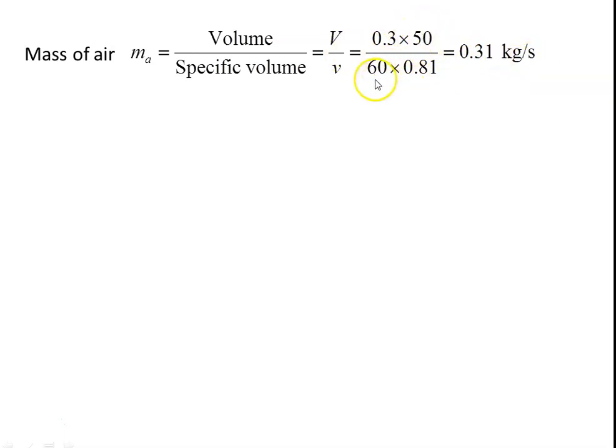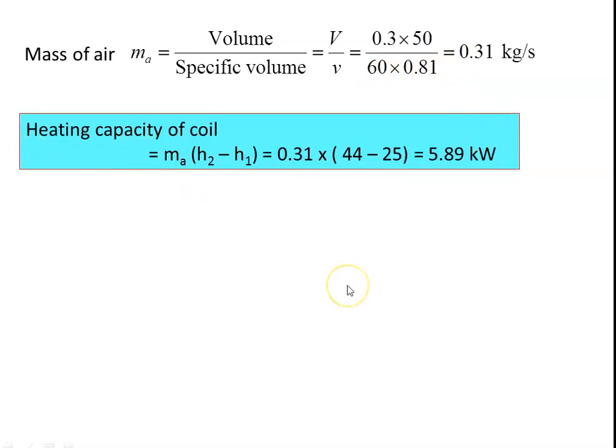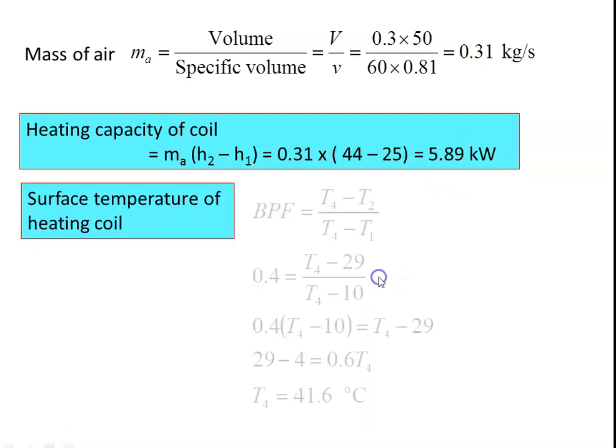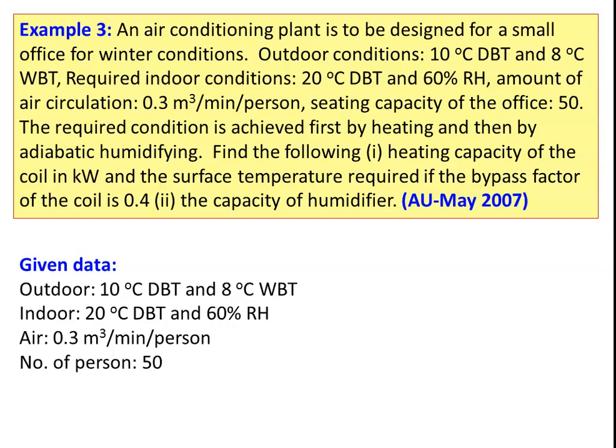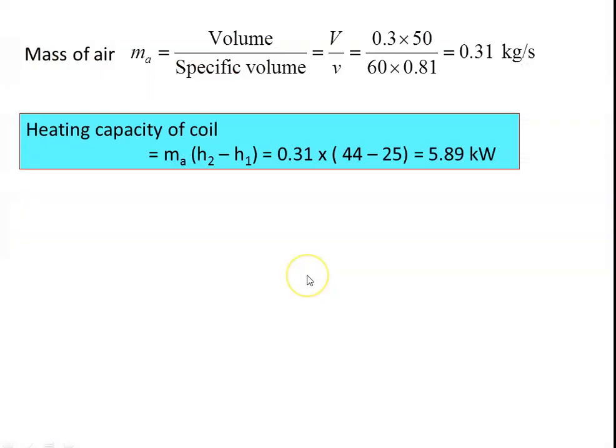Volume is 0.3 m³/min per person, multiplied by 50 persons, divided by 60 (to convert to seconds), divided by specific volume 0.81, giving 0.31 kg/s. Heating capacity of the coil = M × (H2 − H1) = 0.31 × (44 − 25) = 5.89 kW. The bypass factor is given as 0.4.